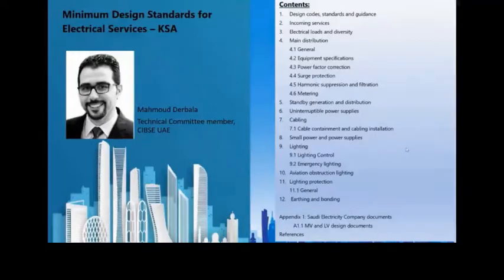Chapter 9 covers lighting design, generally linked to the CIBSE SLL guidance, showing all relevant design considerations from lux levels, uniformity, working plane, mounting height, reflectance values, maintenance factors, and related items like LMF, RSMF, LLMF, LSF. All of those items shall be considered while doing a project in KSA for lighting.